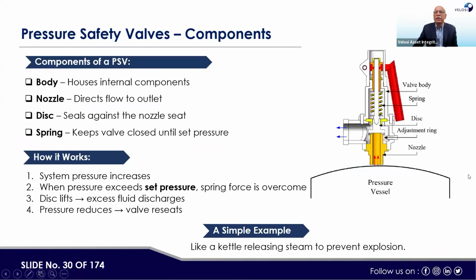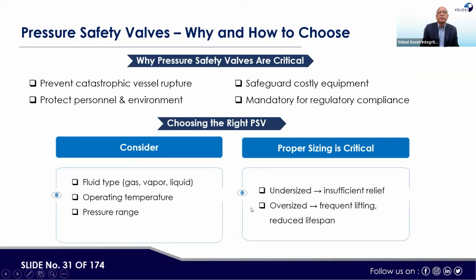Now, if we look at the components of the PSV, here is the spring, valve body, disc, adjusting ring, and the nozzle, below which is the pressure vessel. So: body, nozzle, disc, spring. How it works: system pressure increases. When the pressure exceeds the set pressure, the spring force is overcome, then the disc lifts and excess fluid is discharged to the relief system. Pressure is reduced, and the valve resets or reseats. Like a kettle releasing steam to prevent explosion, just like that.